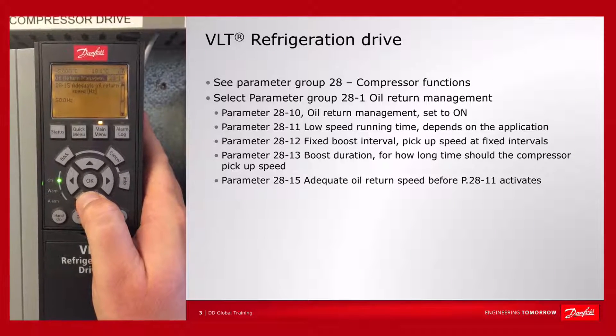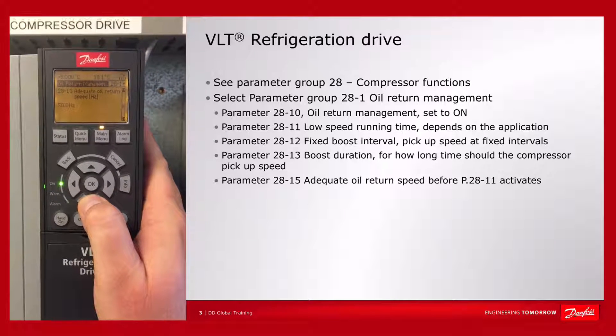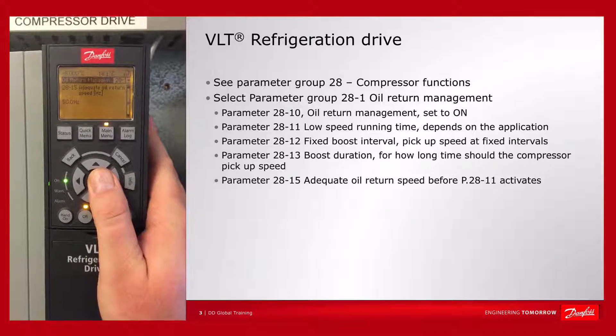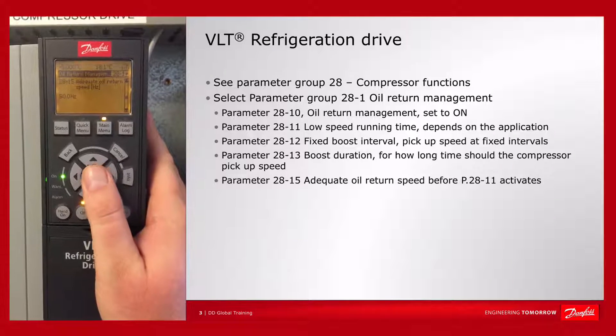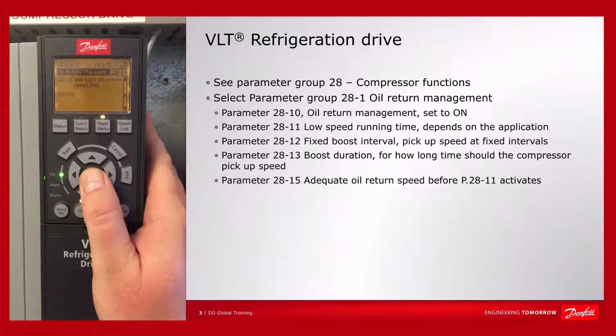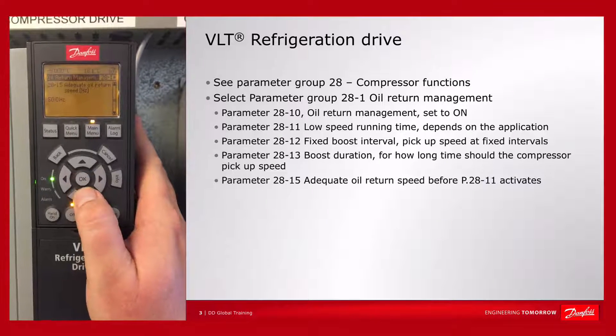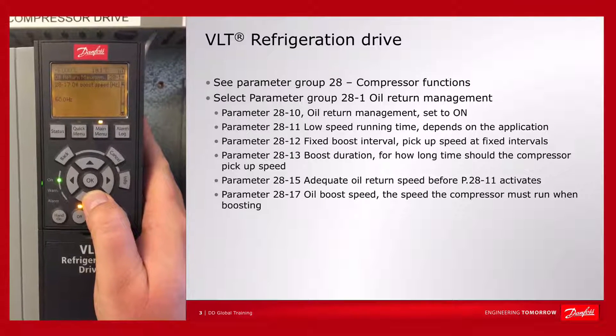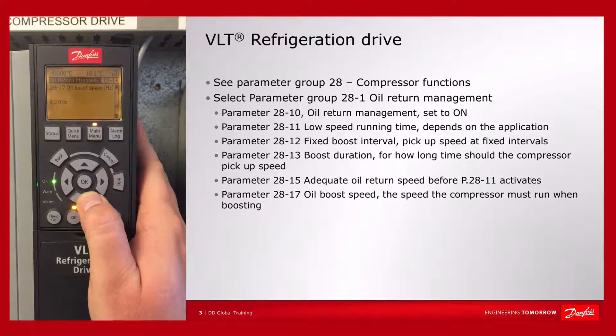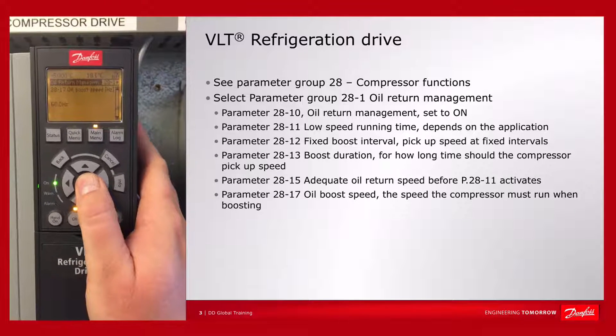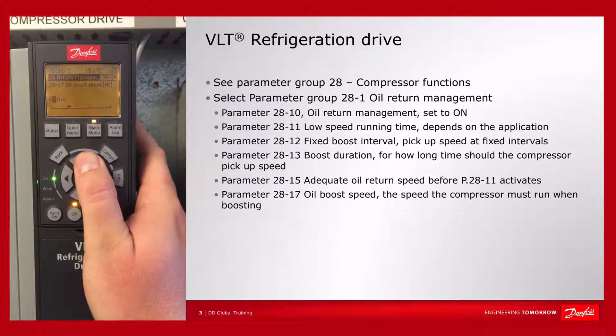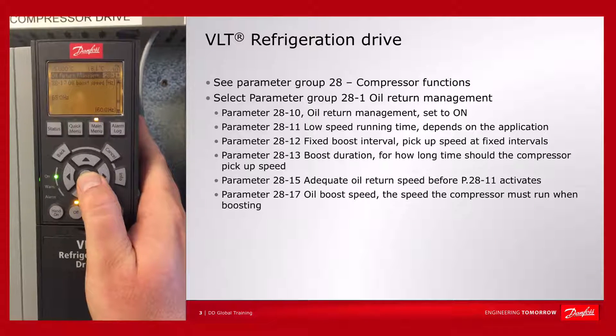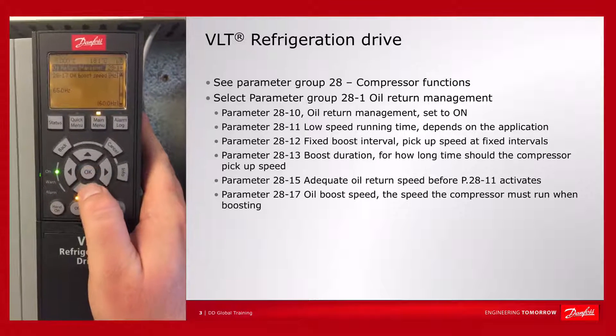Then you must determine at which speed oil is returned adequately to the system. At speeds below 50 Hz, oil is not returned adequately, so we will leave this as it is — it could be 40 Hz or 55 Hz depending on the compressor and system. Then you must determine to which speed the drive should pick up the compressor for oil return management. I will program 65 Hz — again system dependent. This means the drive will pick up speed to 65 Hz when it has been running below 50 Hz for 1 minute.